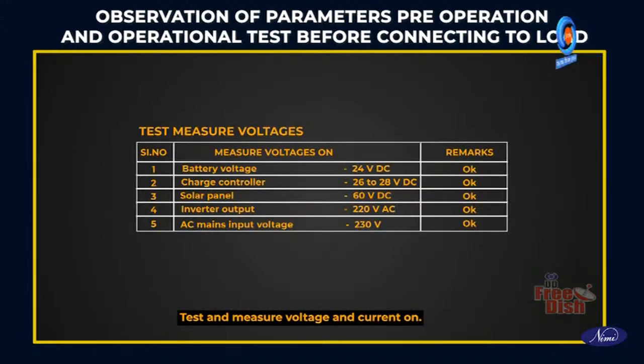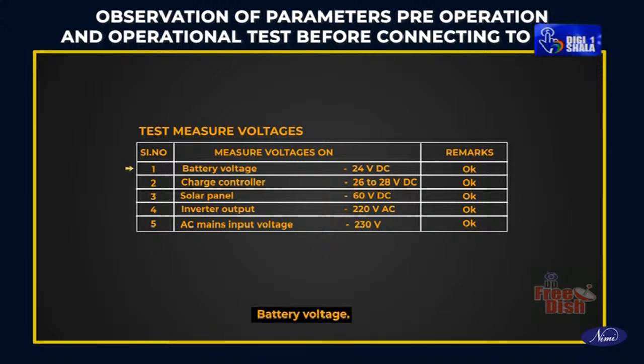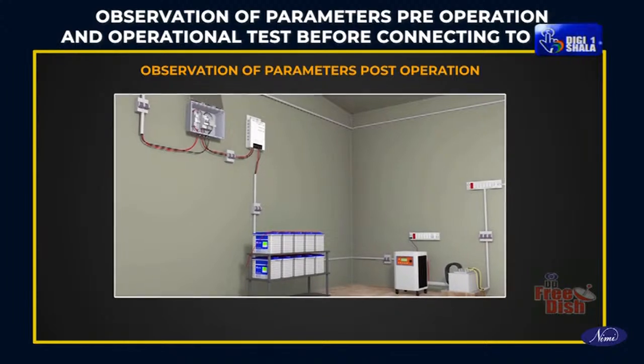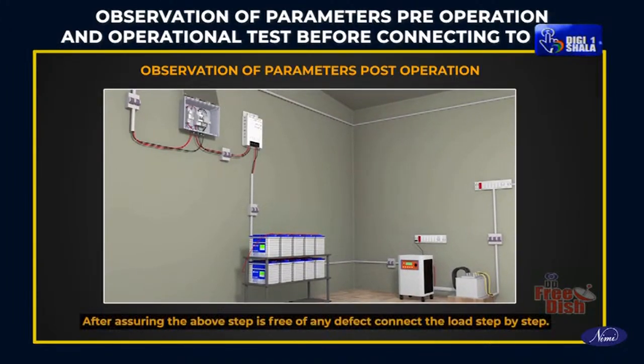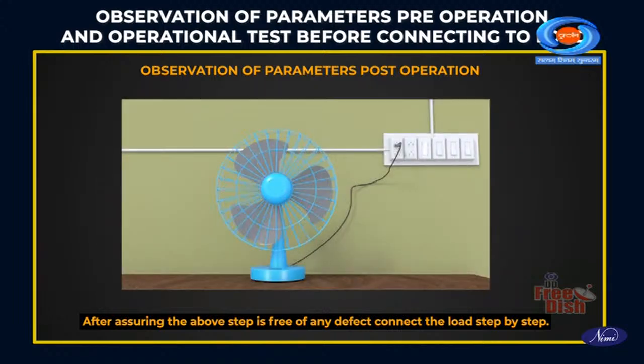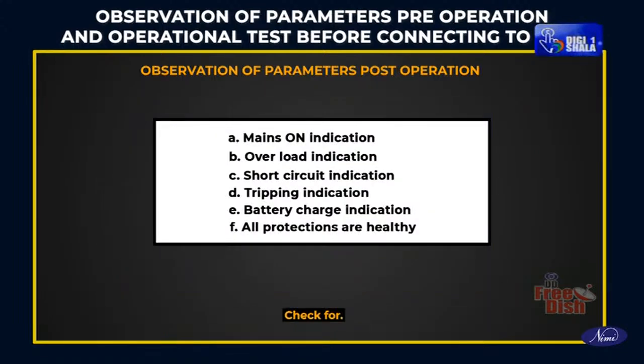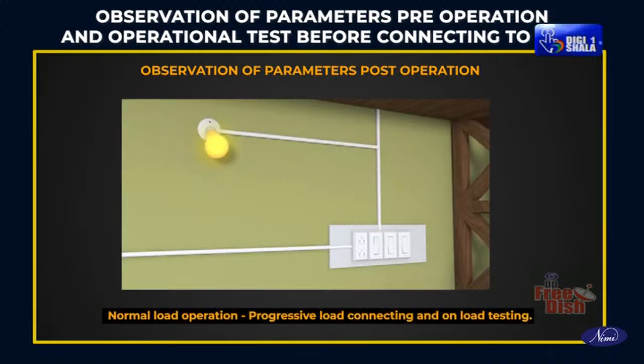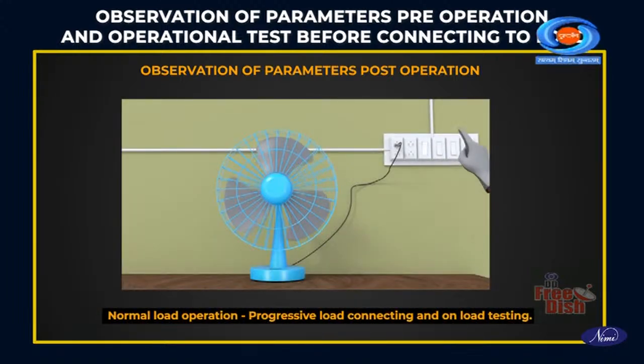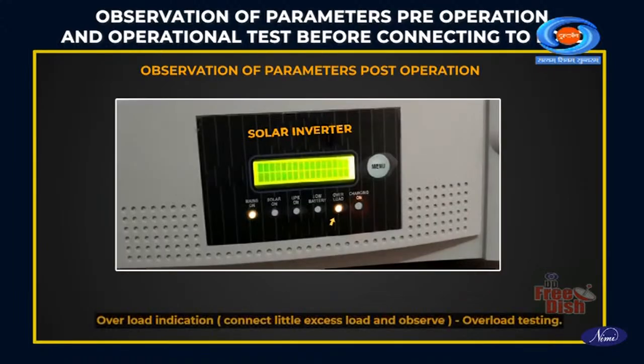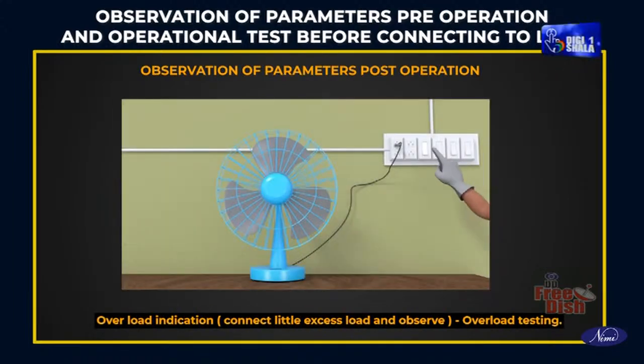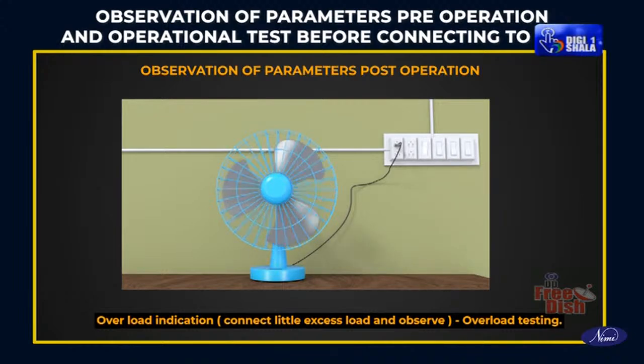Test and measure voltage and current on battery voltage, charge controller, solar panel, inverter output. Observation of parameters post operation. After assuring above step is free of any defect, connect the load step by step. Check for normal load operation, progressive load connecting and on load testing. Overload indication. Connect little excess load and observe.